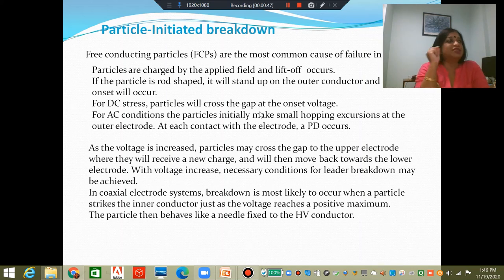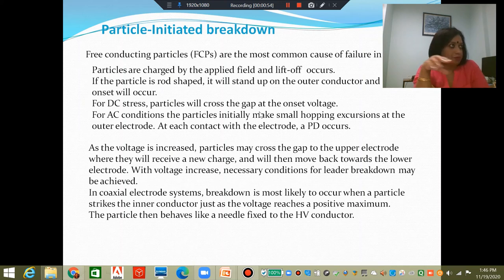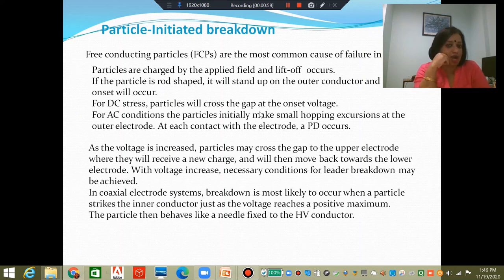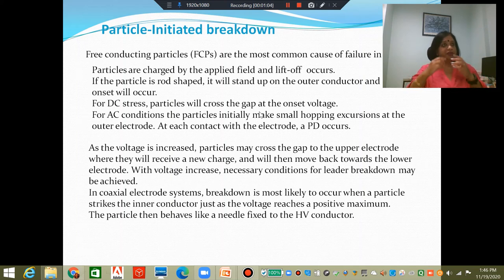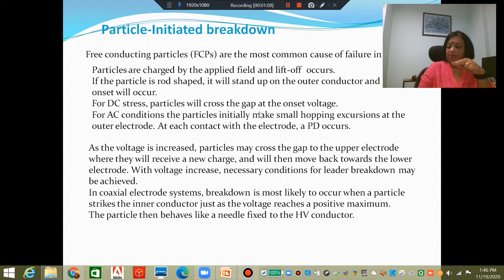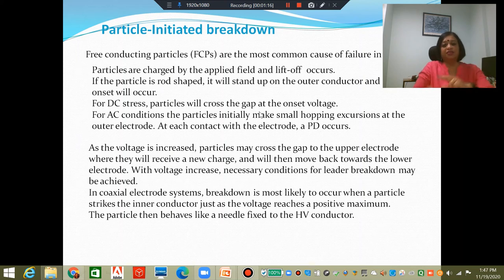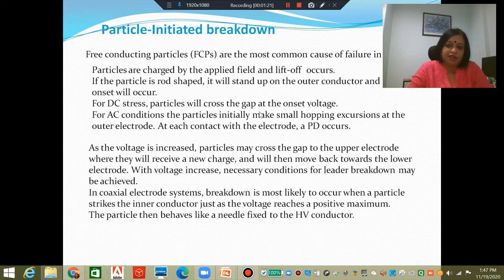When you apply the electric field, these particles get charged. If they are free particles — not attached to any stationary components inside the GIS — these particles can get charged by the applied electric field and will tend to move in the direction of the field. In the coaxial configuration, if on the inner surface of the outer cylinder there are free particles, they will act in the direction of the field and will be lifted off.